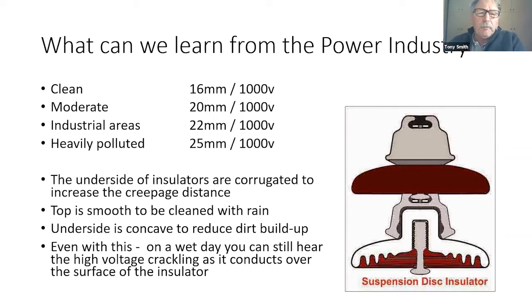Looking at the top, the distances involved are around 16 millimeters for 1,000 volts, radically different from the roughly 1 millimeter needed for an air gap for clearance. So creepage distance is probably the thing that dominates your thinking when you're designing something.